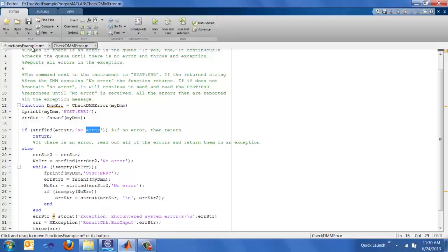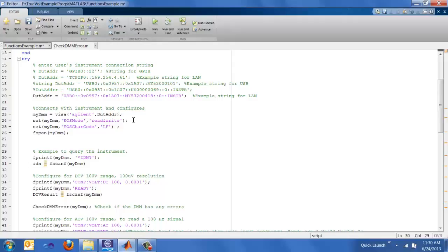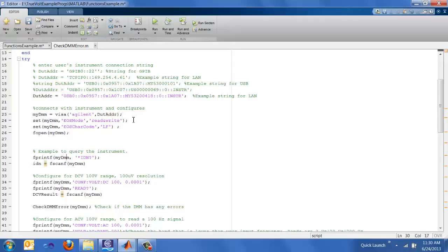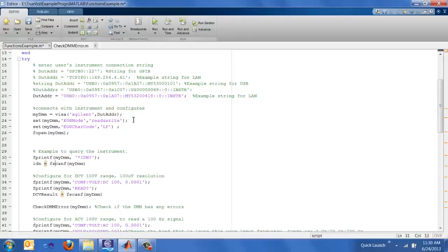Going back to the function examples.m file. I had mentioned about sending commands and receiving commands, but I didn't really actually talk about how you do those. So the easiest way to do that is actually by sending an fprintf statement to the DMM and then followed by the command that you want to send over. That will send the command to the instrument. And then if you want to read the instrument response back, then you do an fscanf into a variable.